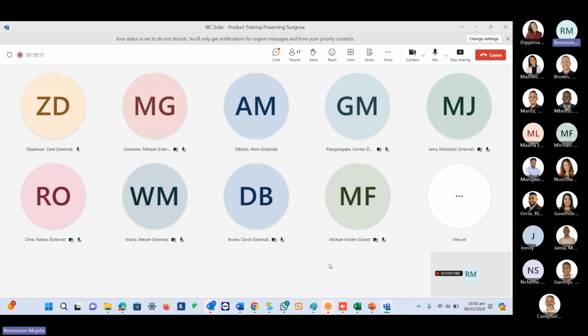So the only thing that you need to do on that, depending on how you are communicating with the logger. So let's say TCP IP. You plug in the switch. Both logger and the controller must be on the same local network. They must be able to see each other. And then under power control, you just tell the logger that you are using remote power control. You just have to select remote power control. So on the slide, you saw the last part where there's local power control and the closed loop thing. That won't be there. It will just be remote power control. As long as it knows that it's remote power control, it becomes a gateway to the iSolar Cloud and access to the settings of the inverters. So it waits for commands on the controller and then tells the inverters what to do. Exactly what is coming from the controller, the inverters will do that. But it still offers you access to the iSolar Cloud, basically, yes. Okay, perfect. Thanks for that.